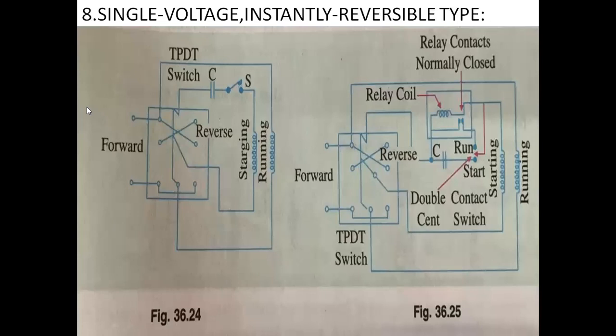Next: single voltage instantly reversible type. If using this type, the motor can be instantly reversed. We take out four leads externally and connect them. However, it is manually done. For instantly reversible operation, we have to do it within seconds. Normally, the motor must be brought to complete rest and then started in the reverse direction, because the centrifugal switch cannot close unless the motor has practically stopped.